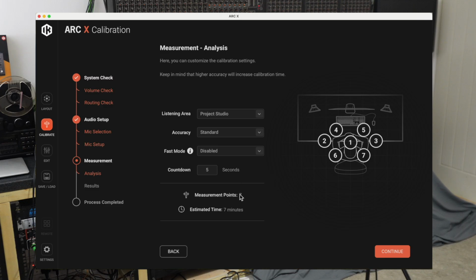And you can now choose the accuracy of the calibration. Minimal is 1 recording. Basic is 3 recordings. Standard, the one we're going to go with, is 7 recordings at these different calibration recording points. And if we then go to advanced, you still see the same 7 calibration recording points, but look down here, it says measurement points 21. If you decide to go for the advanced calibration, you'll be asked to make the 7 calibration recordings at these 7 positions, but at 3 different vertical heights, giving you a total of 21 calibration record points.